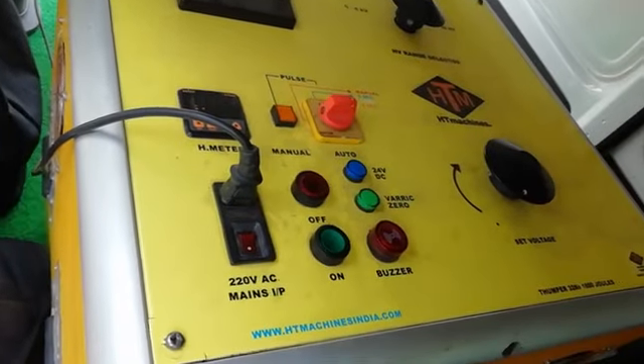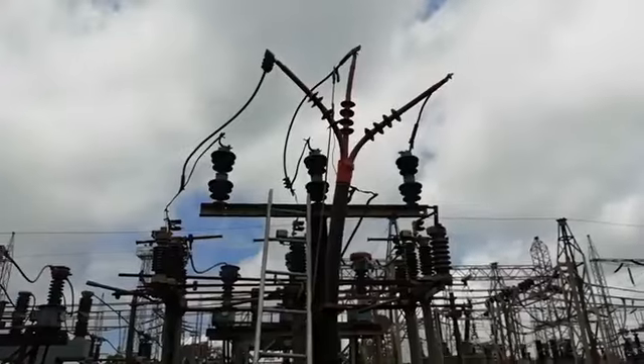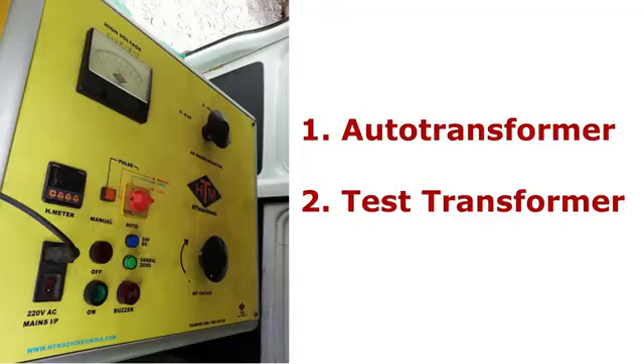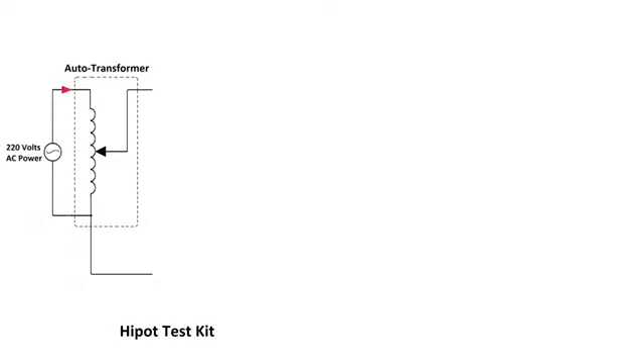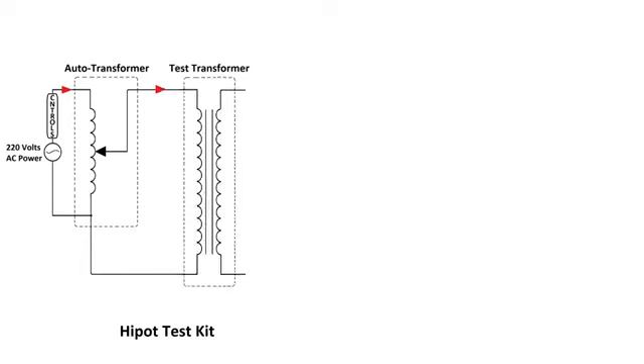This is a DC hipot test kit for testing, and a power cable is the test object. If we look at the components of the kit, we can see an auto transformer and a test transformer are its major components. 220 volts AC power input is given to the auto transformer through a control box, and the auto transformer output is used to adjust the input voltage to the test transformer's primary windings. And the test transformer is used to raise the voltage to the required test level.